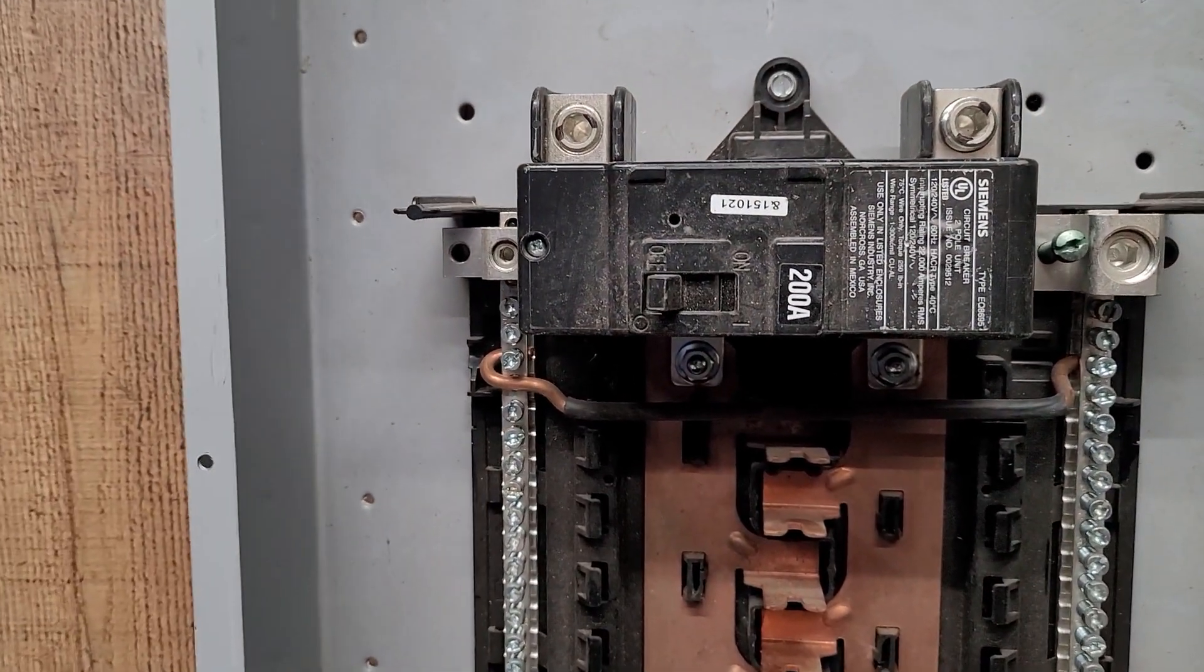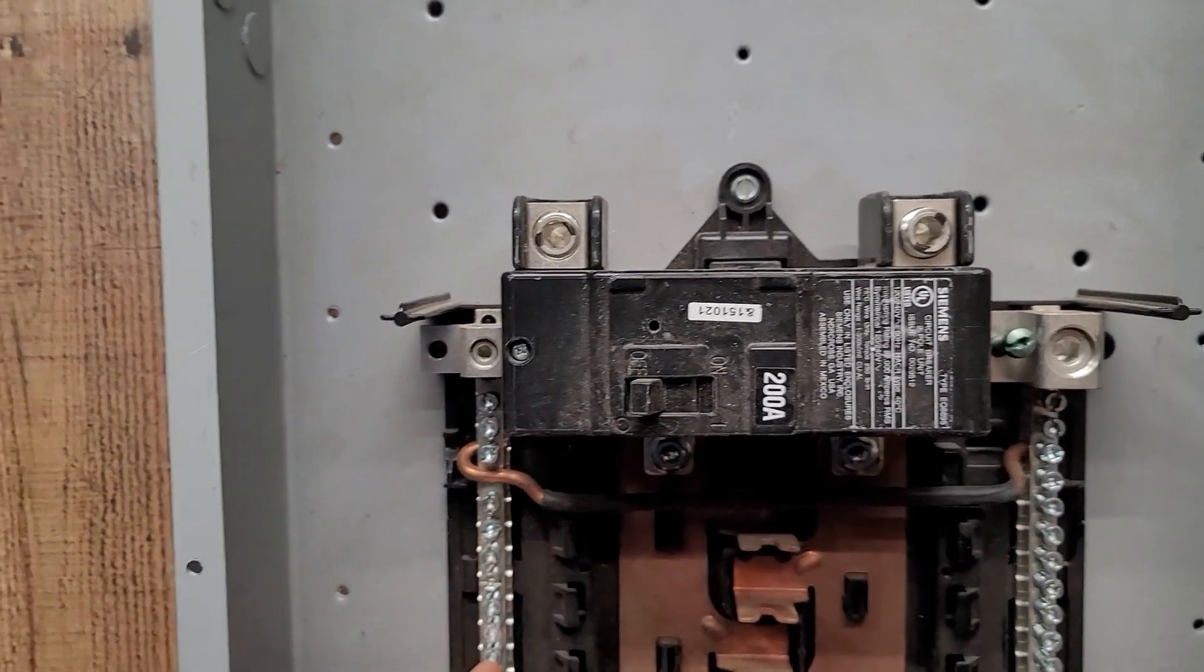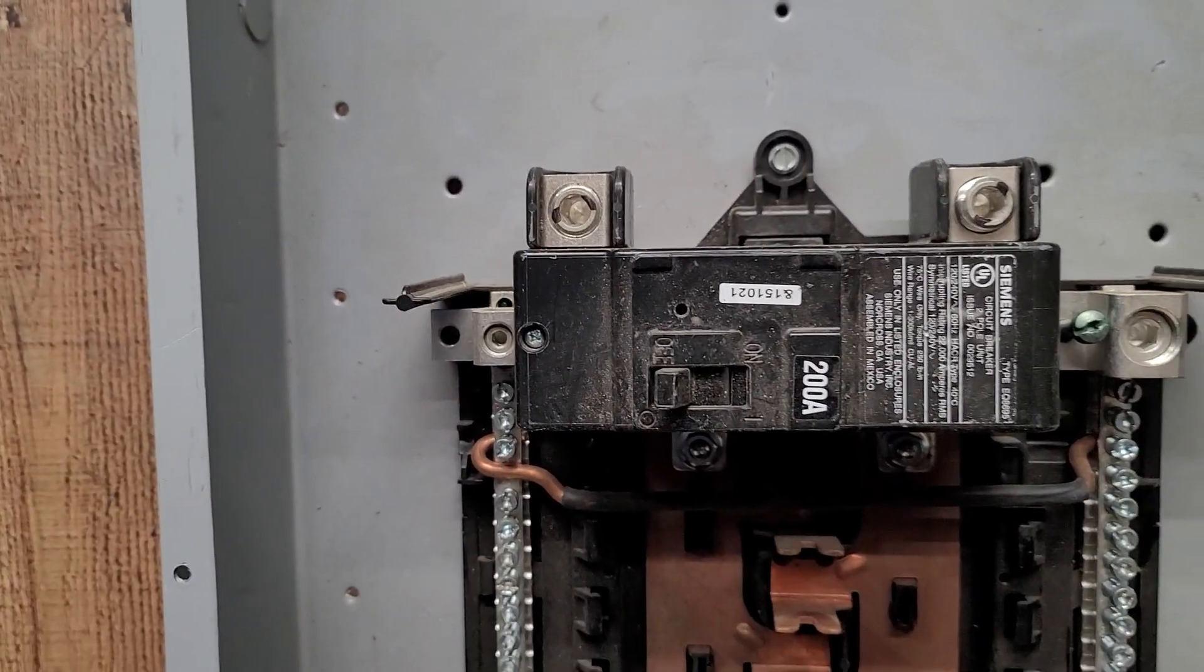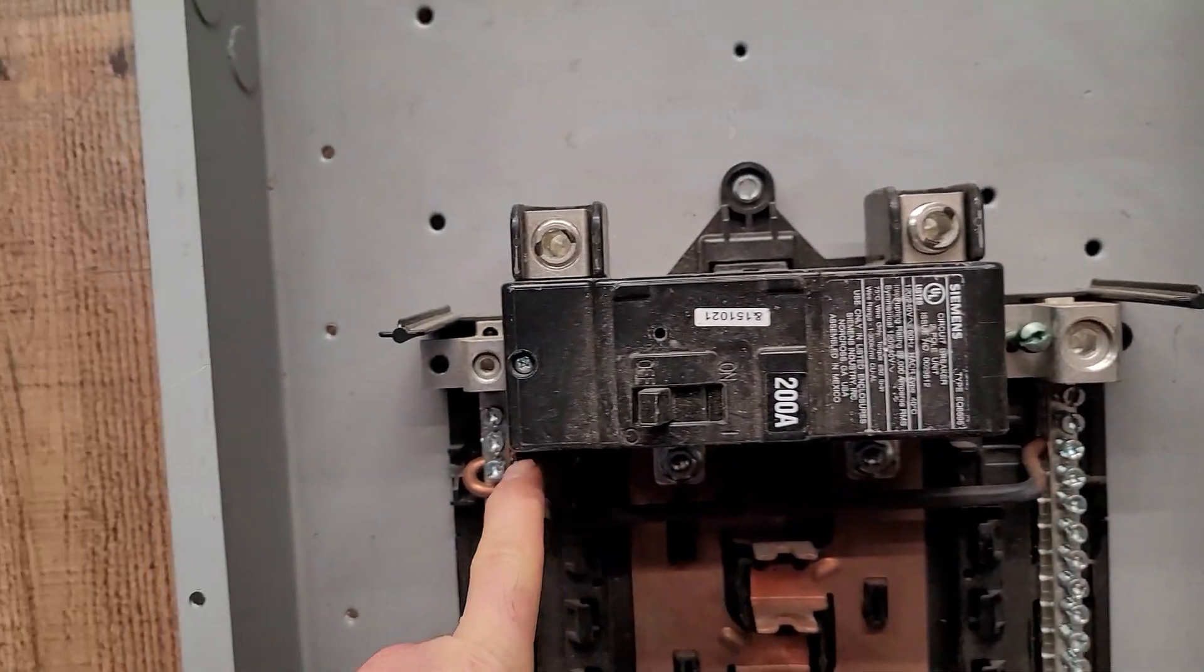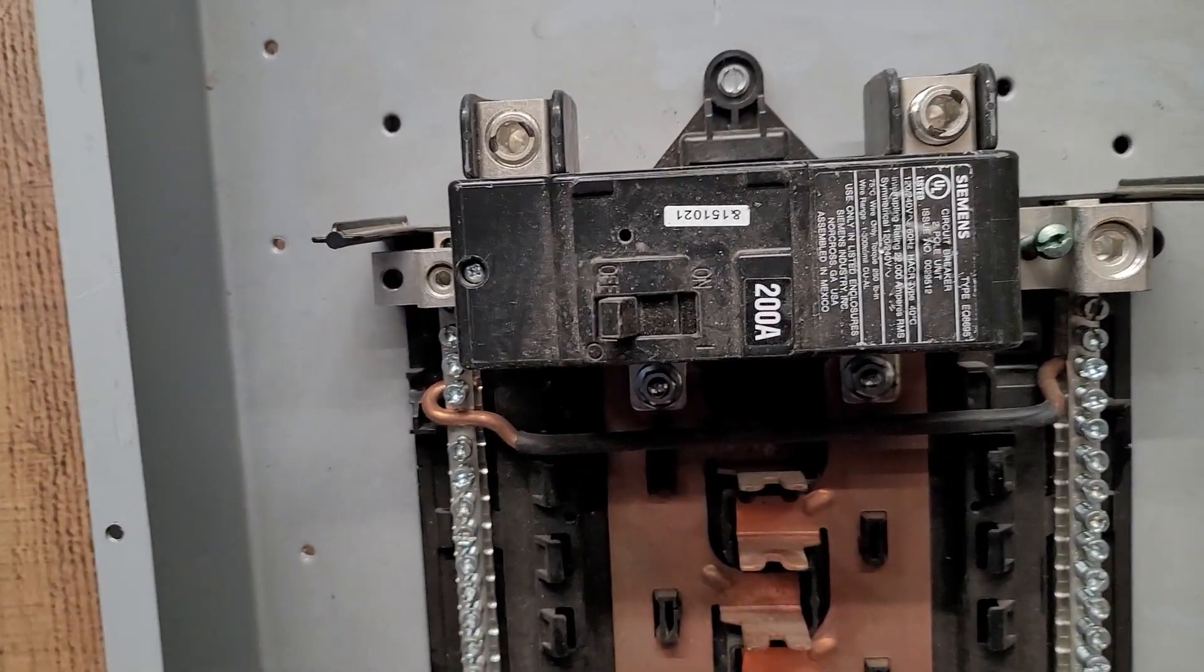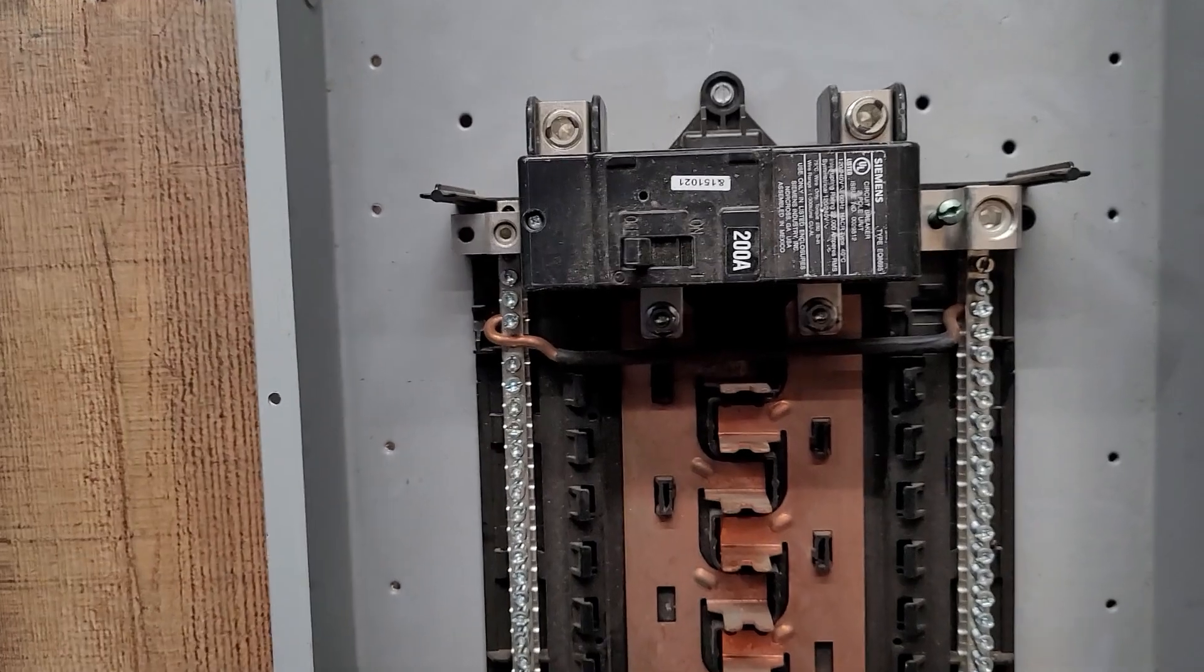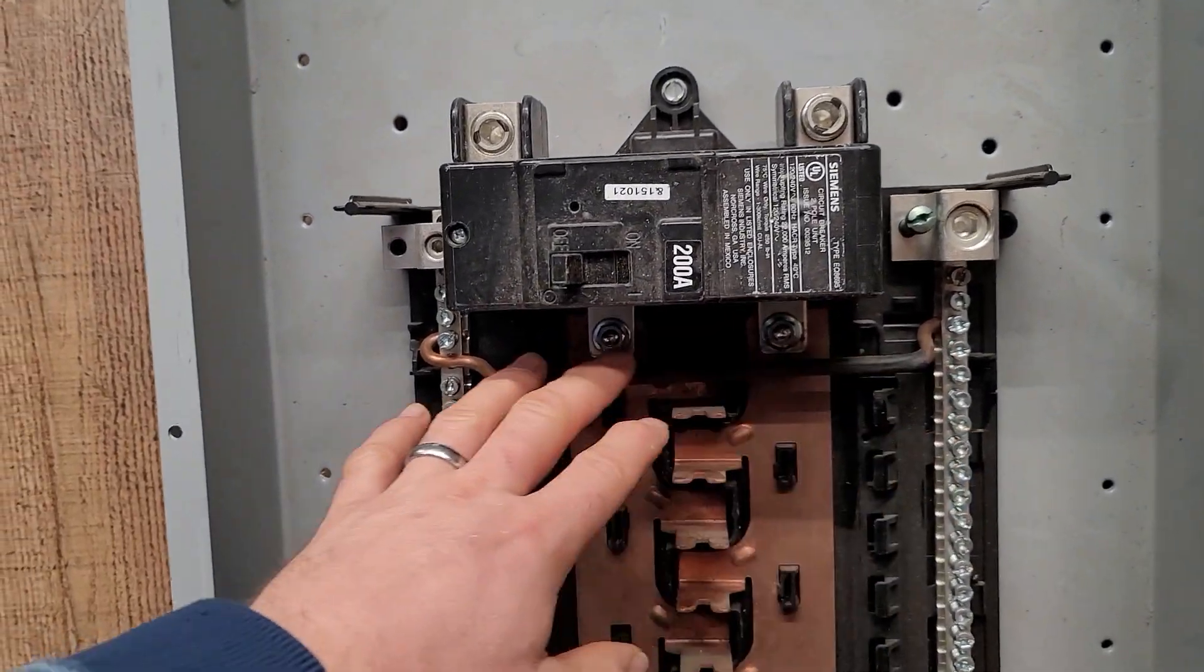So with that being said, if this is the second point of disconnect, one of the temptations is to just pull this bar out. Loosen it here, loosen it there, and pull that bar out. But this is where you got to be really careful. A lot of these panels are not listed to take that bar out.